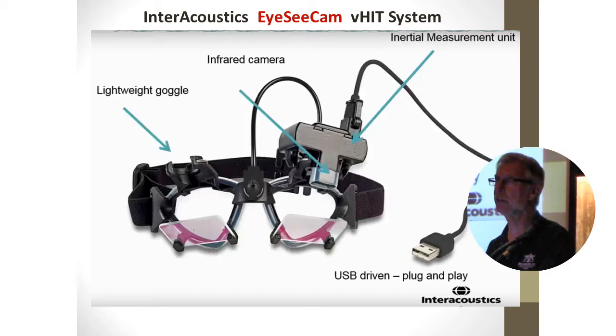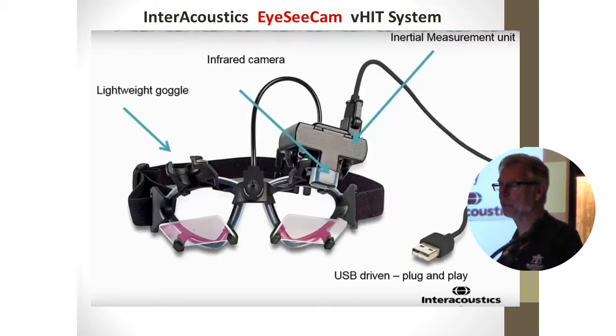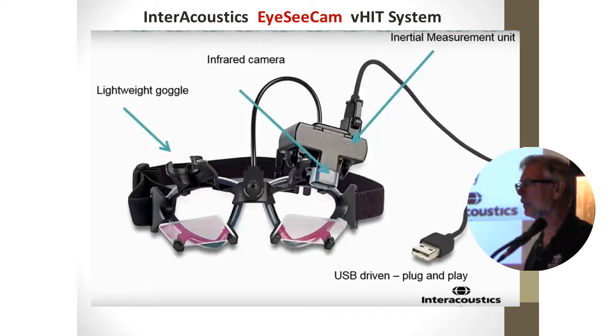You're actually using the vestibular ocular reflex to get this response. So all of the hardware involved in this is this one simple headset. It just contains a very lightweight, very high-resolution infrared camera to record eye movement, as well as a motion sensor to record head movement.